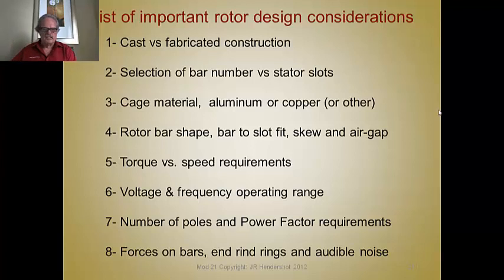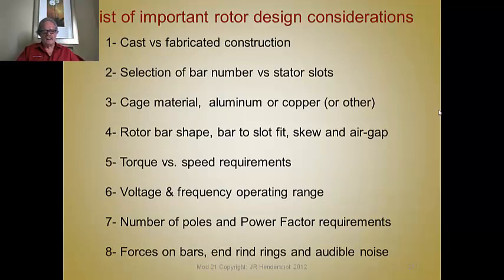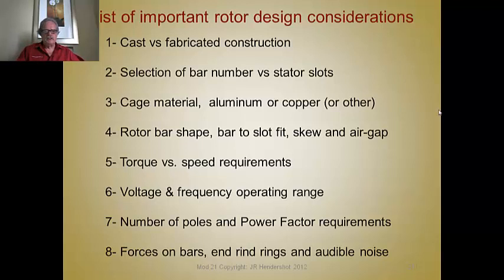Let's start with a summary of the major design considerations. We have to decide first whether we're going to cast this rotor or fabricate it. We have to select a number of bars and rotor slots versus a number of stator slots. We have to select a cage material — aluminum or copper — and then most importantly the bar shape itself and its location, the slot fit, whether it's skewed or not, and of course the air gap between the rotor and the stator.